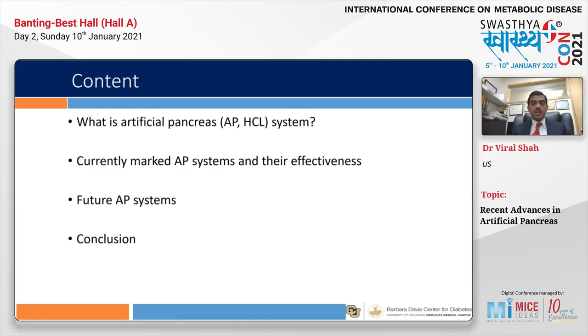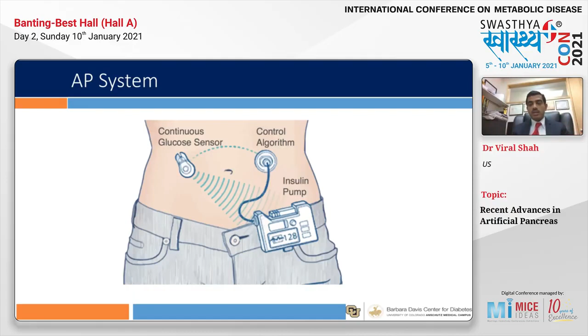So what is AP system? The artificial pancreas system is a very simple concept. If the patient is using an insulin pump, which delivers insulin, and the patient uses a continuous glucose monitor that monitors the subcutaneous or interstitial glucose every 5 minutes, in some CGM systems every 1 minute, we can easily connect the two by means of a mathematical algorithm, which in closed loop system is called the control algorithm. So every minute or every 5 minutes, continuous glucose monitoring glucose can be utilized to deliver insulin through the insulin pump. That's the concept of artificial pancreas system.